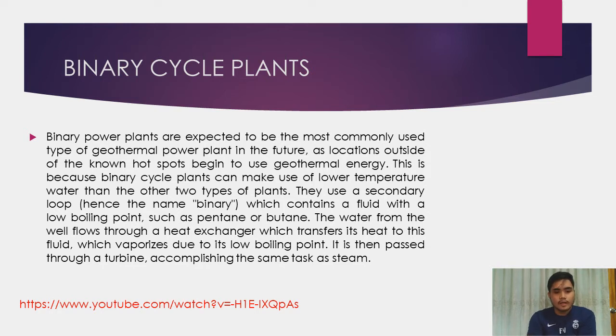They use a secondary loop, hence the name binary, which contains a fluid with a low boiling point, such as pentane or butane. The water from the well flows through a heat exchanger, which transfers its heat to this fluid, which vaporizes due to its low boiling point. It is then passed through a turbine, accomplishing the same task as steam.